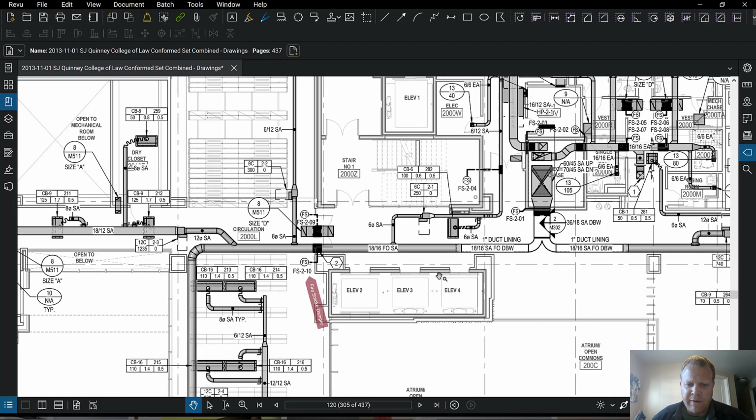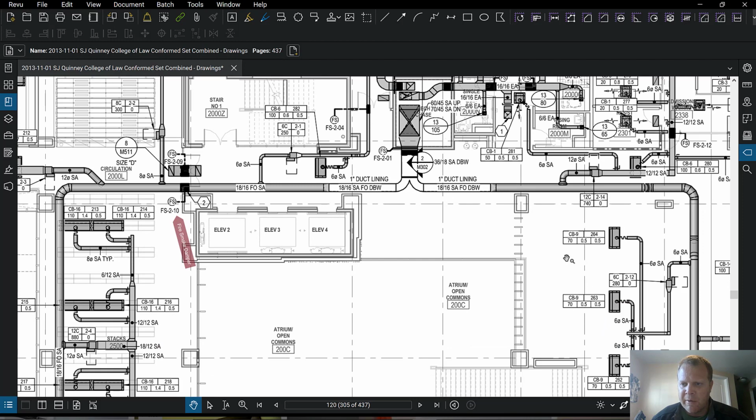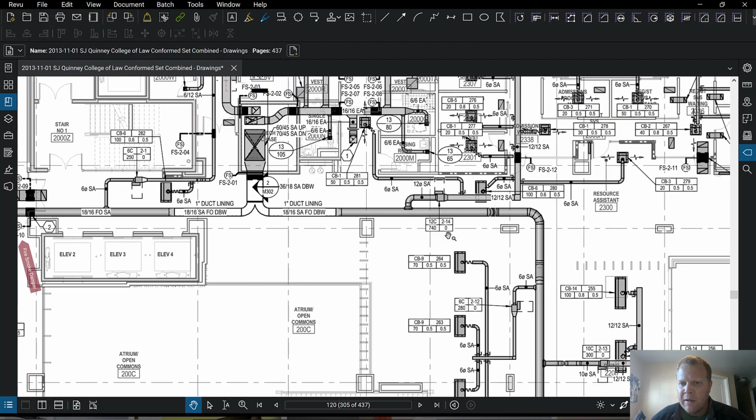If you cannot follow what we're seeing, we have the atrium here, you have doors, and this whole space right here is sort of like the elevator stair lobby idea, right? So have all this area right here. I bet you could find more if we went into find these other doors. Yep, there's another door with a ductwork smoke damper there.